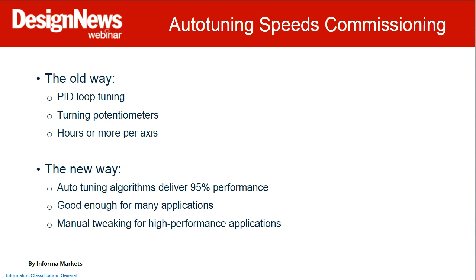They're also able to do adaptive tuning. Part of the built-in functions are tunable filters. In the case of drives, you can have anti-slosh routines, which is always kind of a treat to watch on YouTube. They'll exercise the drive and it'll be ping-ponging all over the place. The drive takes that information and adjusts the filtering. You exercise the drive again, and the motion is really smooth and not problematic. So you've got that capability now.